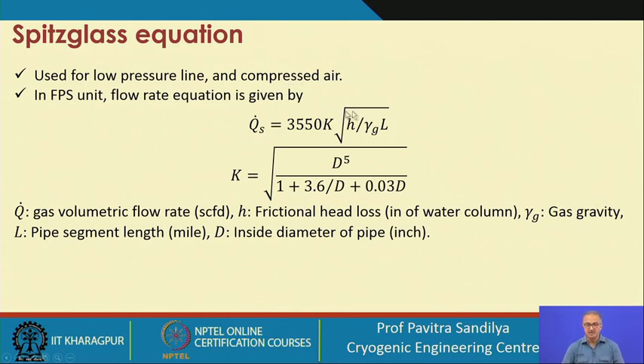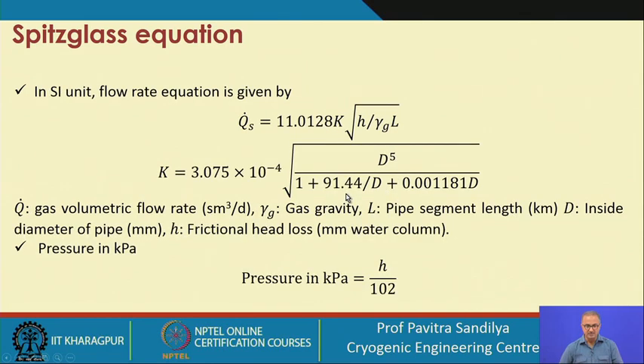There is another equation called the Spitzglass equation, generally used for low pressure lines. This is the expression for the Spitzglass equation, where H is the frictional head loss in inches of water column, and the gas gravity and the coefficient K are given in terms of the inside diameter of the pipeline. The similar expression is given for SI units, where the coefficient values have changed for the different unit systems.